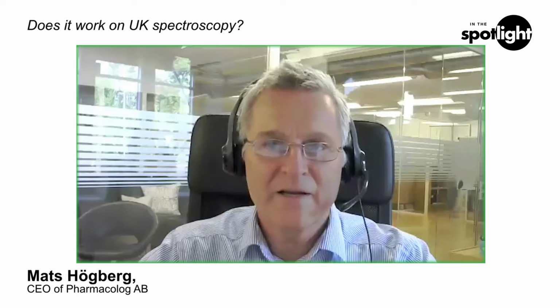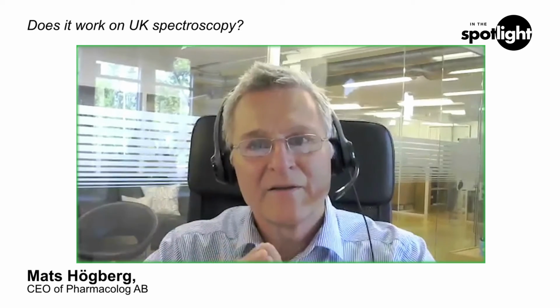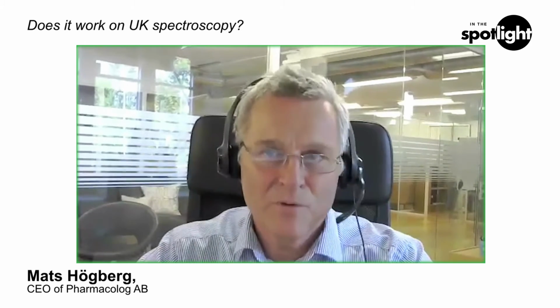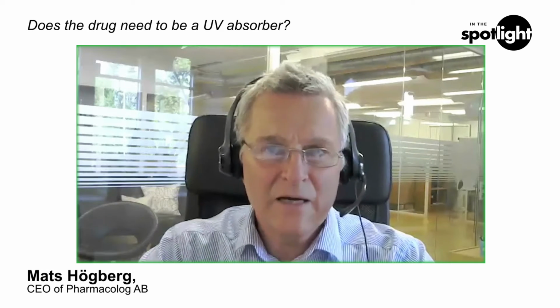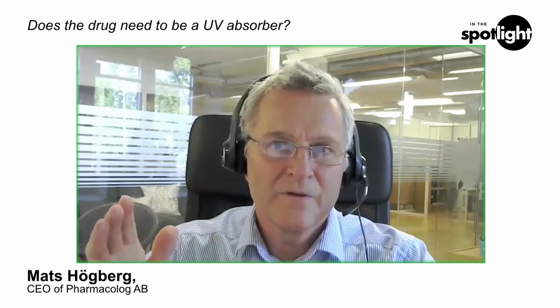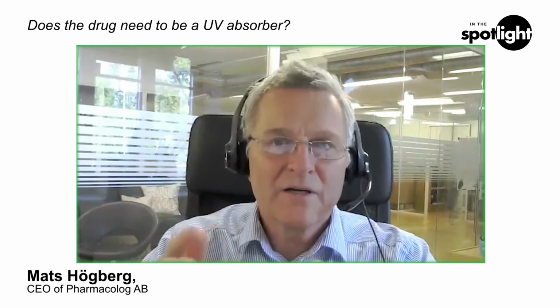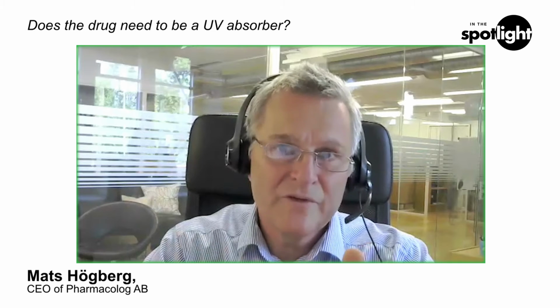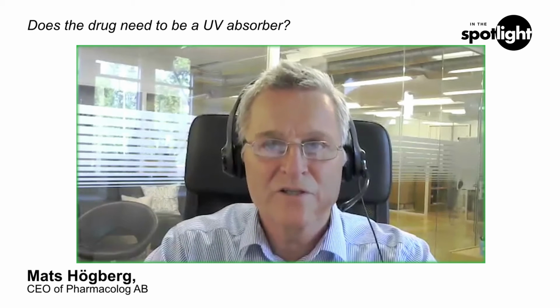Remind me, it works on UV spectroscopy, I think. Yes, that's correct. It's UV-Vis. We go from 200 nanometers up to 800, and we look at the complete spectrum, which is an important thing for the system to work well. So the drug needs to be a UV absorber? Well, not necessarily. It could also absorb around other wavelengths, because we look at the complete curve. If you have an absorption around 400 or 500 nanometers, which is not in the UV field, we will see that as well, and we will build a calibration so that we can recognize it and determine concentration.